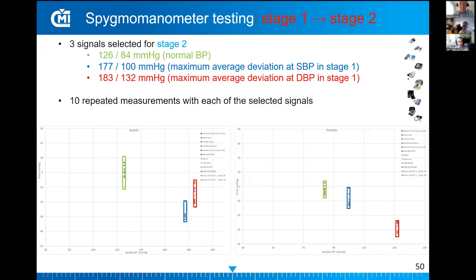As I mentioned, there was also stage 2 of this testing. This stage 2 consisted of 3 signals that were used in the first stage. The first one of these signals represented normal blood pressure measurements, 126 millimeters over 84 millimeters of mercury, and this signal was used as a representative of normal blood pressure measurements, with the goal to evaluate the repeatability of 10 repeated measurements for each of the devices. Then 2 more signals were used, both representing a hypertensive patient. The first one, 177 millimeters over 100 millimeters of mercury.